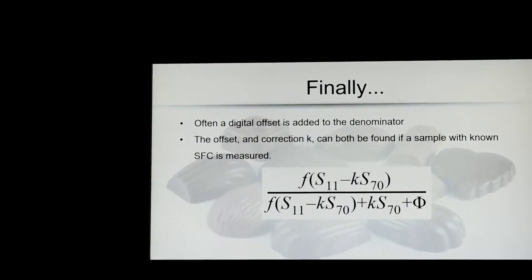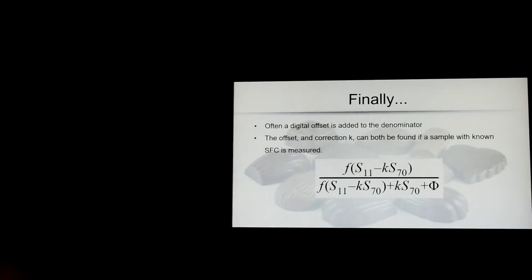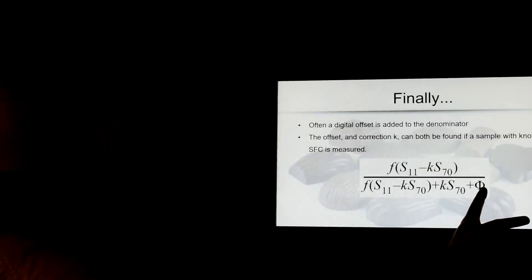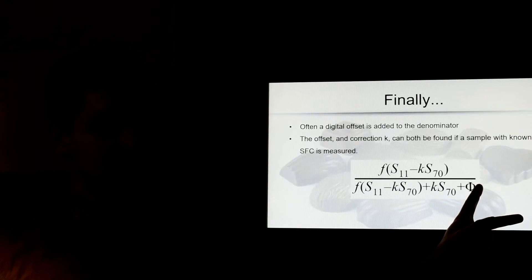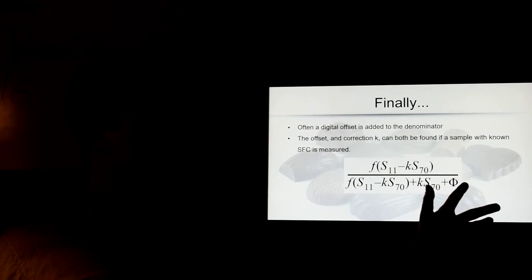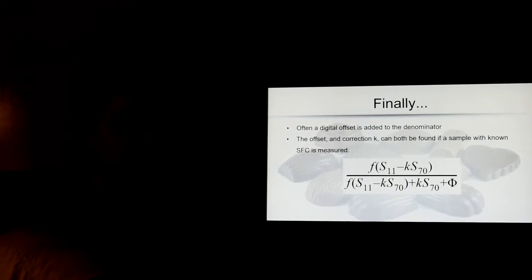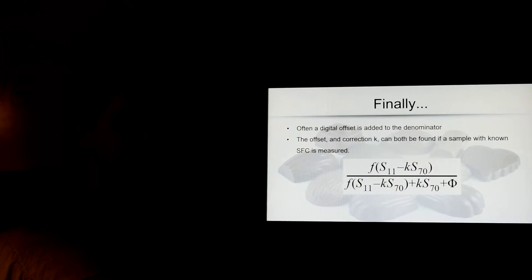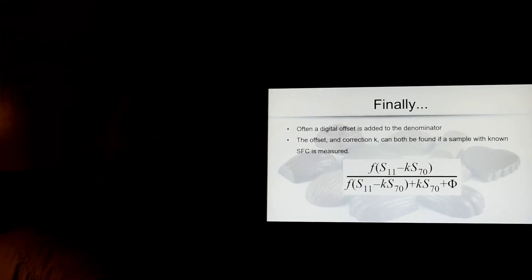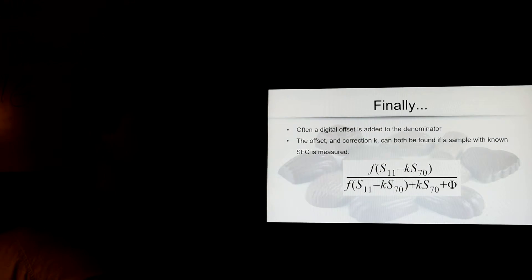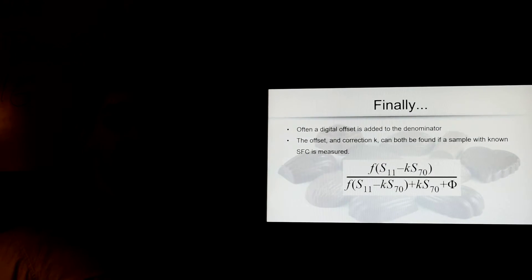Finally, some companies give you a digital offset. That is a constant that you add to the denominator right there. It depends on the equipment, and the program used, and the computer, and so on. To find F and K, you simply measure a sample with a known amount of solid, usually that's mineral oil with a piece of plastic with known concentrations. And then you find it every day through a calibration.